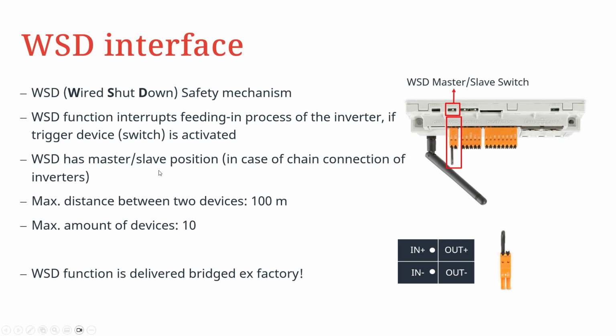But with this wired shutdown, it makes it possible that by the push of the trigger switch, which is usually a normally closed button, you can automatically shut down the entire system, even if it is one inverter or more than one inverter. So this WSD switch basically interrupts the feeding process of the inverter if the trigger switch is activated, just as explained in the earlier instance I have given you. So the WSD has a master-slave position. So in the case where you have a multiple connection of inverters, we will definitely implement a master-slave protocol, which will be explained in the coming slides. The recommended maximum distance between two devices is 100 meters, and then the maximum recommended number of devices to be connected is 10.